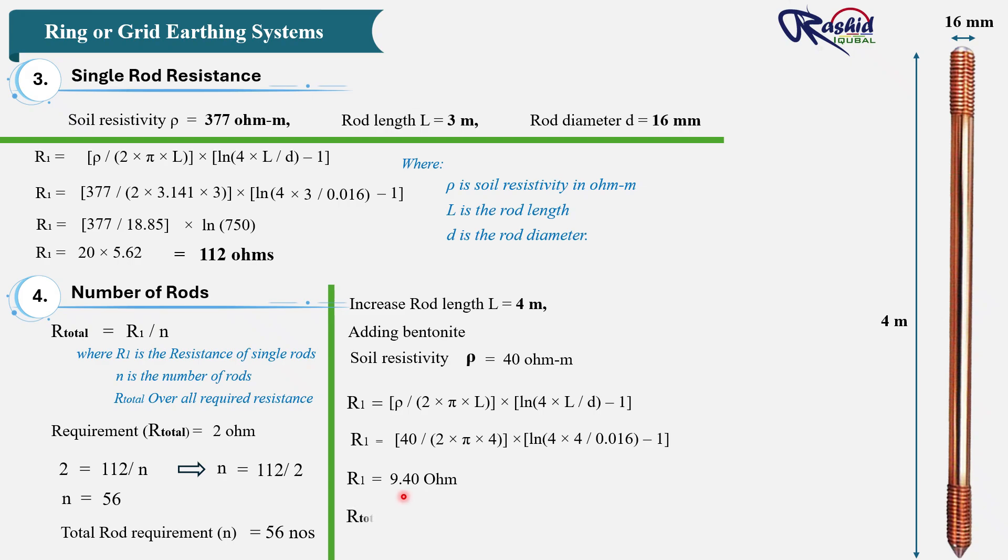So we need to calculate how many rods are required to achieve 2 ohms. So we know the formula: R_total = R₁ / N. R₁ we have here is 9.40 ohm divided by N, we don't know how many rods required. So after solving this equation, we get N = 4.7. So let's take a round figure, 5. We require 5 number of rods. So this is practical and economical compared to the 56 rods. By using longer rods, improving the soil, and adding a buried copper ring, we can achieve a reliable earthing system with fewer rods and lower cost.